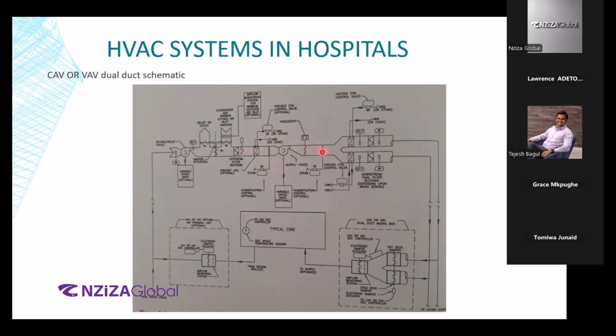This point to this point will also have a pressure drop. So all of that in the air handling unit, from this point to this point, will be the internal static pressure. What is outside, right? From this all the way up to the last VAV box coming out of the diffuser, that might be over here. That will be your external. Internal plus external will give you the total static pressure available for the air handling unit. When designing that, the fans will come into the picture. That is why fans end up becoming a hot topic when it comes to energy analysis. Because the more pressure drop you have in your system, the bigger your fan needs to be, the bigger your motor needs to be, and it will consume more power.